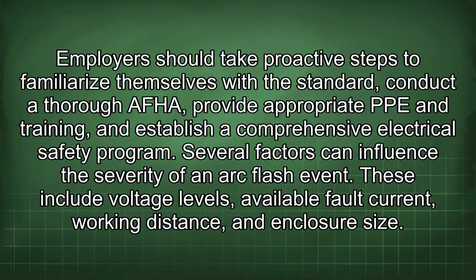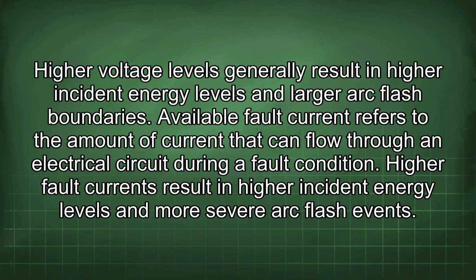Several factors can influence the severity of an arc flash event. These include voltage levels, available fault current, working distance, and enclosure size. Higher voltage levels generally result in higher incident energy levels and larger arc flash boundaries. Available fault current refers to the amount of current that can flow through an electrical circuit during a fault condition. Higher fault currents result in higher incident energy levels and more severe arc flash events.